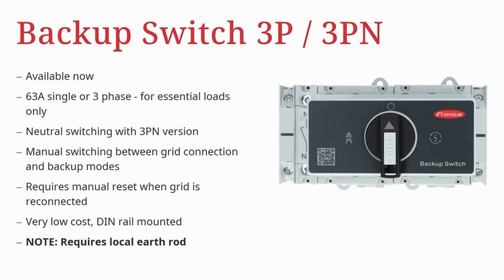The backup switch is available as the 3P and 3PN variants. 3P means three-phase, but also works as a single-phase device, and the N means neutral switching. We recommend that UK and Ireland customers go for the 3PN device. It has a 63 amp switching load, which means that for residential installations where the incoming supply is 63 amps, this device can cover the whole house.